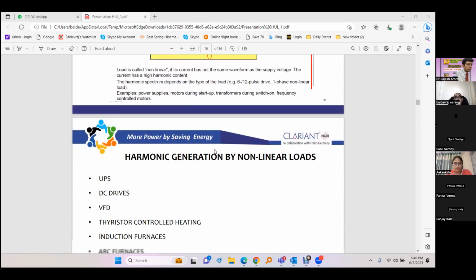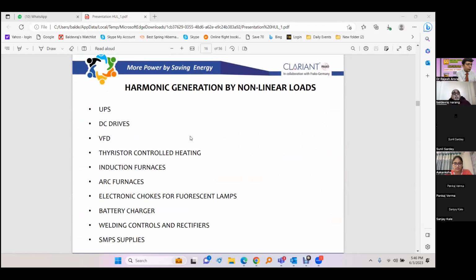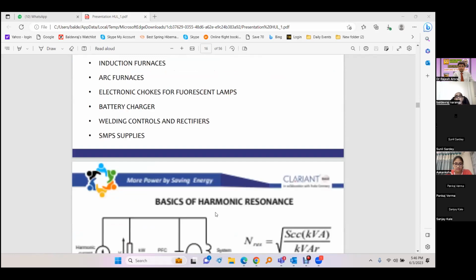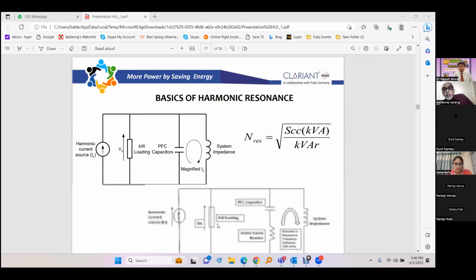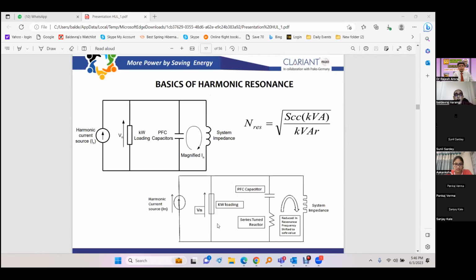So what are these non-linear loads? More than 70% of loads today are non-linear, like UPS, DC drives, VFD, thyristor controlled heating, induction furnaces, arc furnaces, electronic chokes. All lighting, in fact, is non-linear today, whether it is CFL or LED or fluorescent lamps, everything is non-linear. Then battery chargers, welding control, rectifiers and SMPS supplies. So here is another slide which explains how the harmonics affect the system and how we are solving it by passive as well as active means.